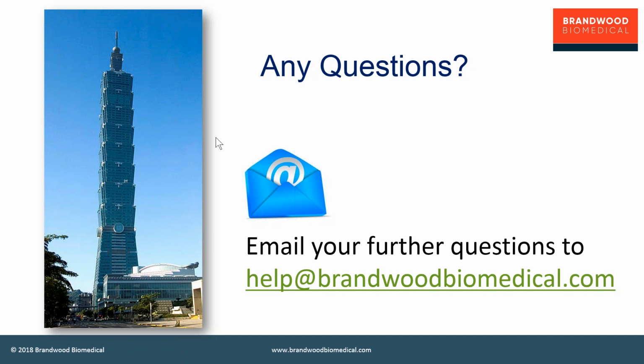Not really—if you have technical changes like indication, any actions of the medical device, or any addition of product specifications, then notification is typically required. Technical content of the IFU requires a variation submission. Tidying up the format, changing the format, etc., does not. Okay, that's clear, thank you.